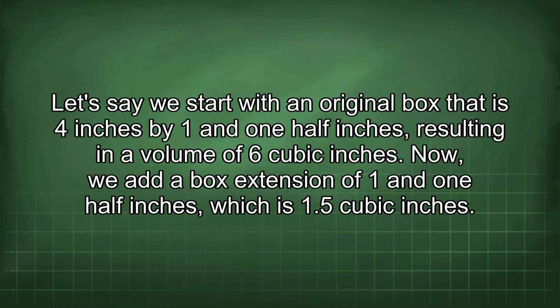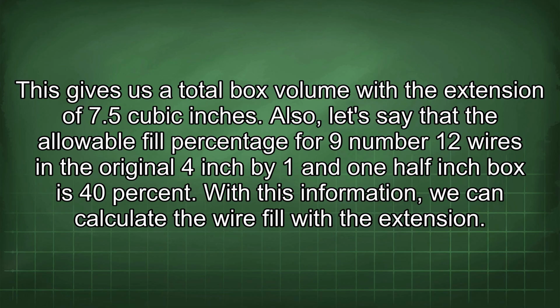Let's say we start with an original box that is 4 inches by 1½ inches, resulting in a volume of 6 cubic inches. Now, we add a box extension of 1½ inches, which is 1.5 cubic inches. This gives us a total box volume with the extension of 7.5 cubic inches.